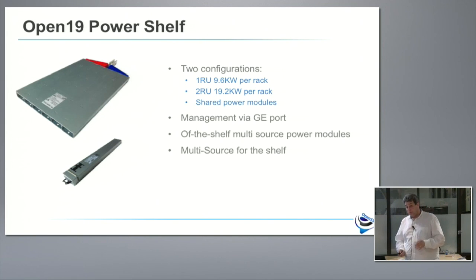We have a 1RU 9.6 and a 2RU 19.2, depending on your configuration on the rack, the location, and how much you can actually consume. If you take a 9.6 or 19.2 and want to push full 400 watts for every server, you have to run a power management system. If you don't want to run a power management system, you limit your servers to 250 watts, and then you don't have to run anything—it will work by itself.